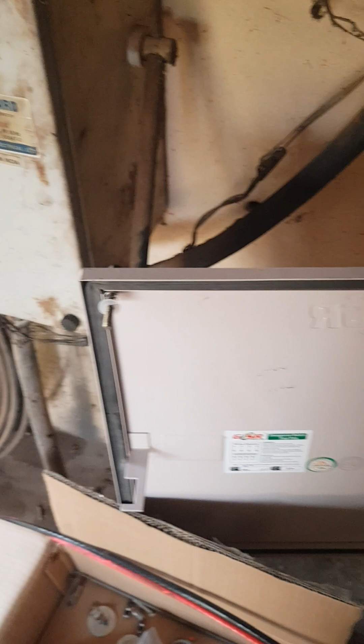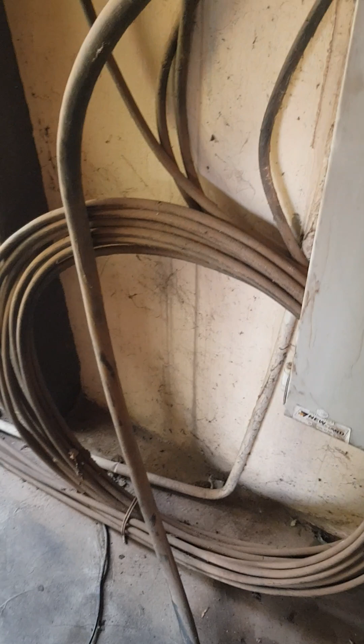Another critical point for this kind of installation is that you need very good earthing. Most installers don't bother about earthing; they don't do a separate one and just connect to the house earthing. This can be very dangerous, because if the house earthing is no good and anything happens, the whole installation will be under serious threat.